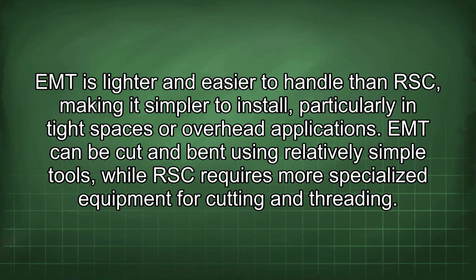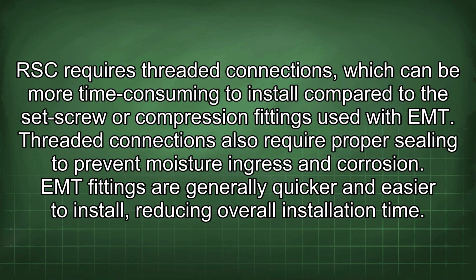overhead applications. EMT can be cut and bent using relatively simple tools, while RSC requires more specialized equipment for cutting and threading. RSC requires threaded connections, which can be more time-consuming to install compared to the set screw or compression fittings used with EMT. Threaded connections also require proper sealing to prevent moisture ingress and corrosion. EMT fittings are generally quicker and easier to install, reducing overall installation time.